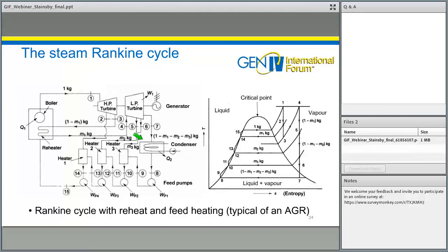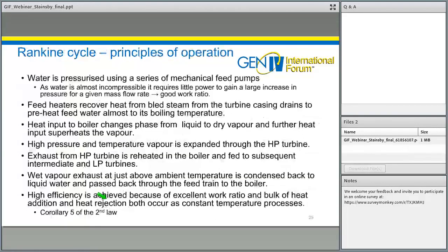And this power cycle is typical of an advanced gas-cooled reactor in the UK. It's a bit more complicated than you find on a pressurized water reactor because we can't get up to such high temperatures on a pressurized water reactor, therefore we don't have things like reheat, and we have very little in the way of superheat. So it's a very standard cycle, pretty much unchanged from what you'd see for the last 100 years worth of coal-fired power stations.